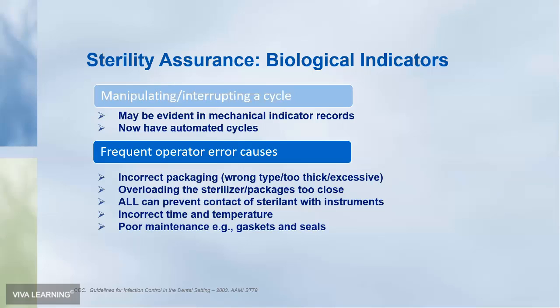So there are racks that will provide the correct amount of space between packaged cassettes and that will allow the sterilant to get in between those spaces and penetrate the packaging. So that's one example. There are also side-on racks that will allow you to place paper plastic pouches at an angle as well, with sufficient separation between them for the sterilant to get in there. All of these causes can actually prevent contact of the sterilant.